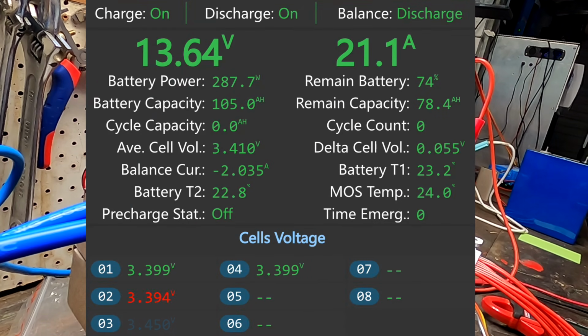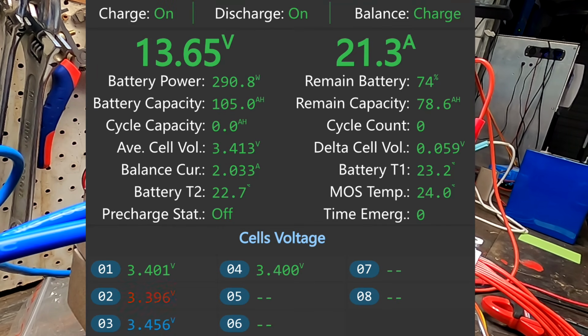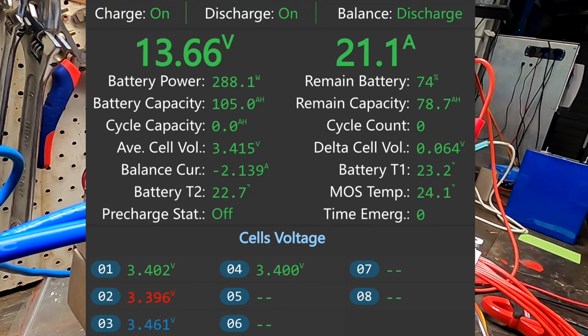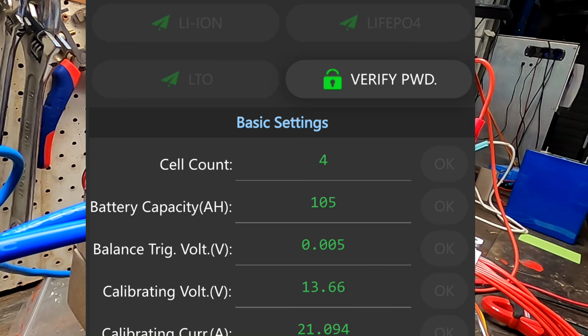And we are discharging cell number 3, which is blue and flashing. Blue means it's the highest voltage cell, and flashing means it gets balanced. So it's now charging the internal supercapacitor inside the JK-BMS. Once this is fully charged, like now, it discharges this energy into the red cell, which is our lowest voltage cell. And it will do the balancing until all the battery cells are under 3.45 volts or under 5 millivolt deviation, what we have set there.